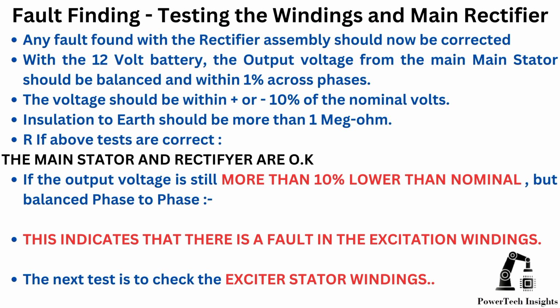With a 12-volt battery, the output voltage from the main stator should be balanced and within 1% across phases. The voltage should be within plus or minus 10% of the nominal volts. Insulation to earth should be more than 1 megaohm. If the above tests are correct, the main stator and rectifier are okay. If the output voltage is still more than 10% lower than nominal, but balanced phase to phase, this indicates that there is a fault in the excitation windings.